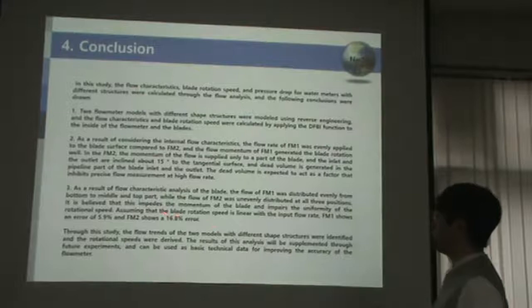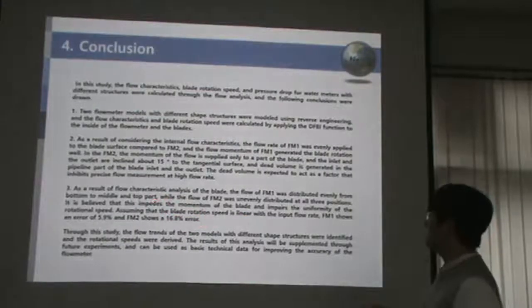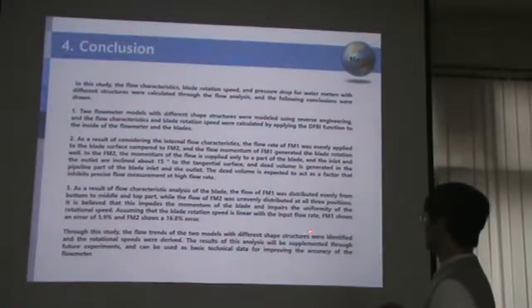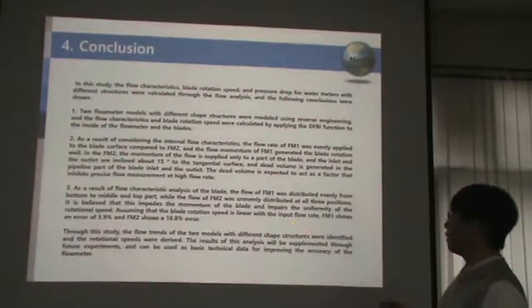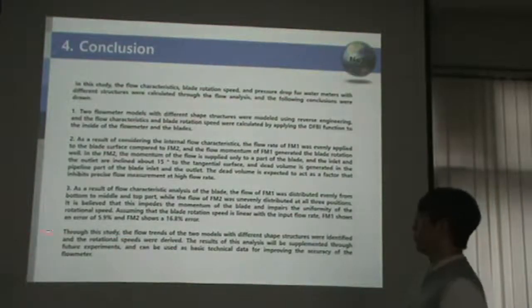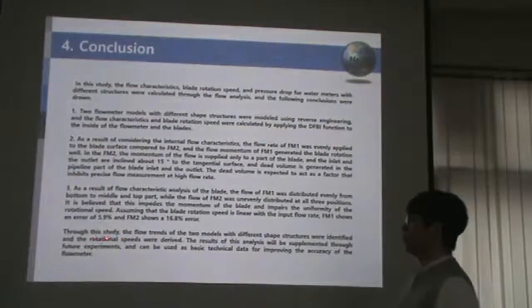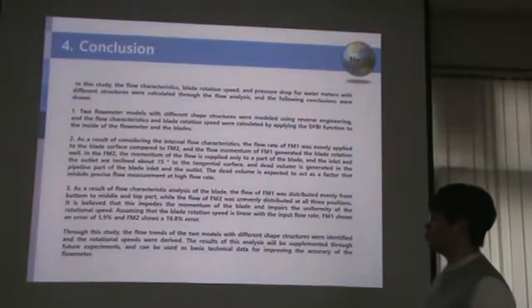Assuming that the blade's rotation speed is linear with the input flow rate, FM1 shows an error of 5.9% and FM2 shows a 16.8% error.